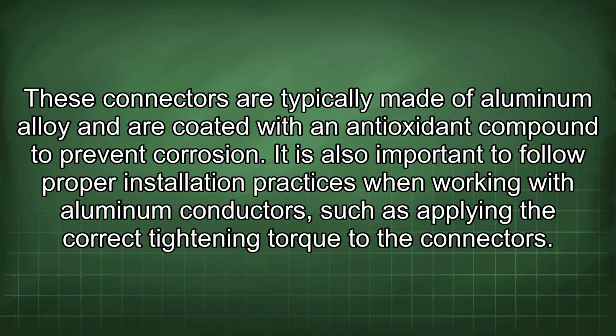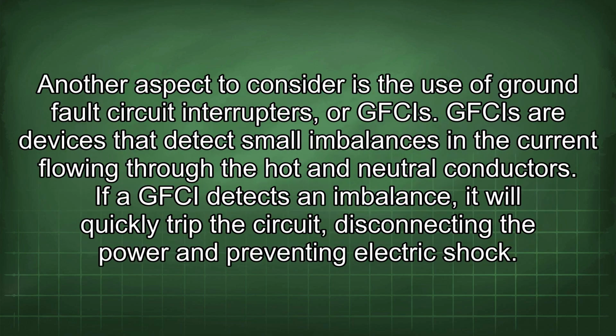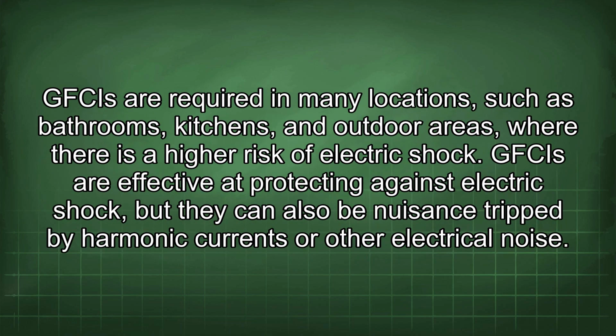torque to the connectors. Another aspect to consider is the use of ground fault circuit interrupters, or GFCIs. GFCIs are devices that detect small imbalances in the current flowing through the hot and neutral conductors. If a GFCI detects an imbalance, it will quickly trip the circuit, disconnecting the power and preventing electric shock.